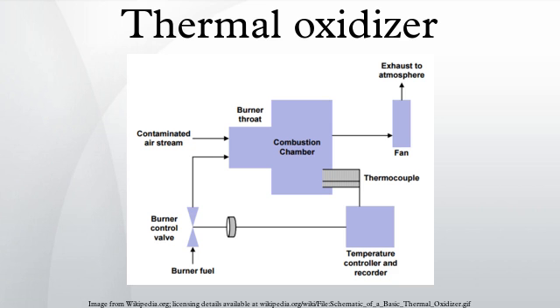Also called afterburners in cases where input gases come from a process where combustion is incomplete, these systems are the least capital intensive, but when applied incorrectly, the operating costs can be devastating because there is no form of heat recovery. These are best applied where there is a very high concentration of VOCs to act as the fuel source for complete combustion at the targeted operating temperature.